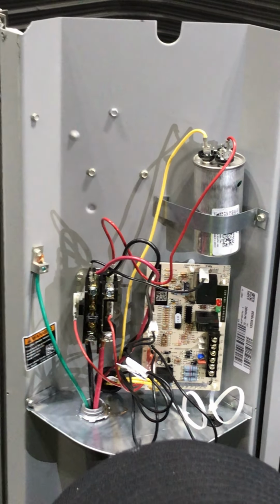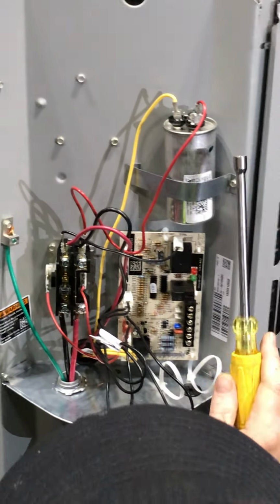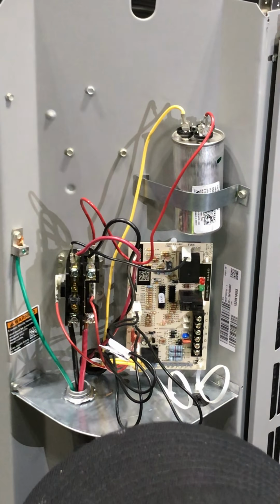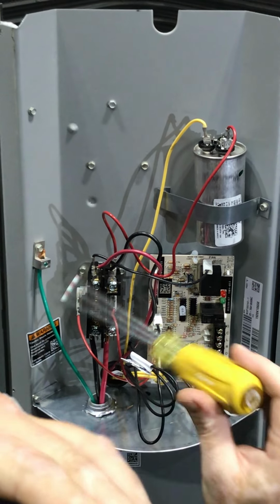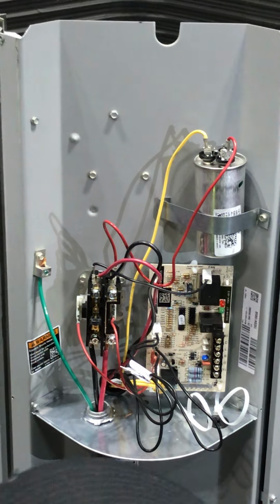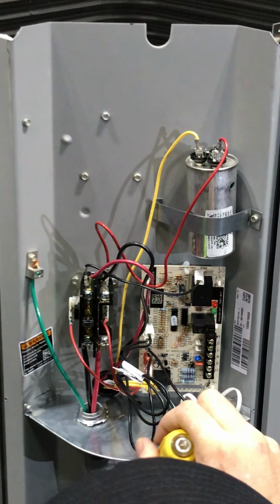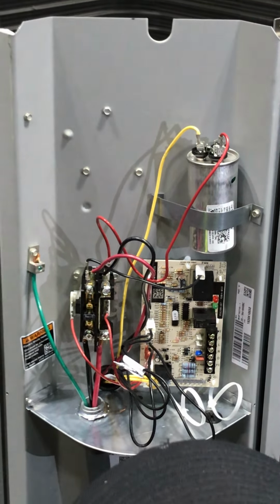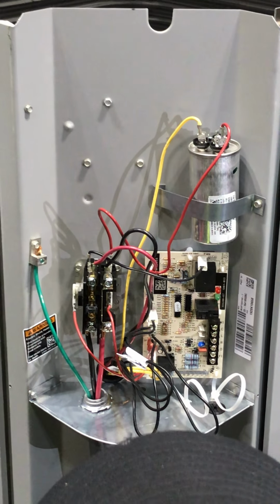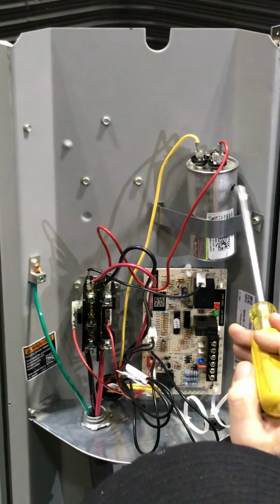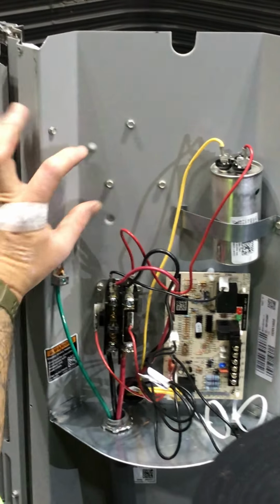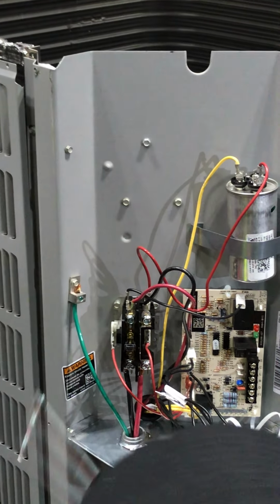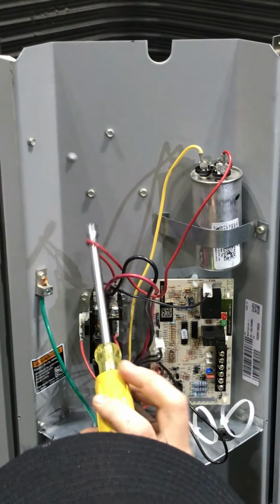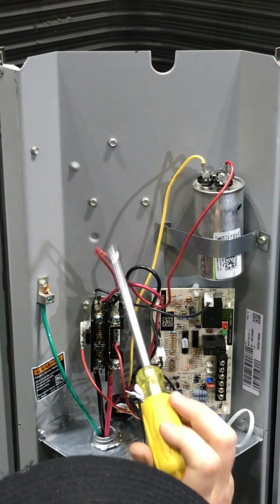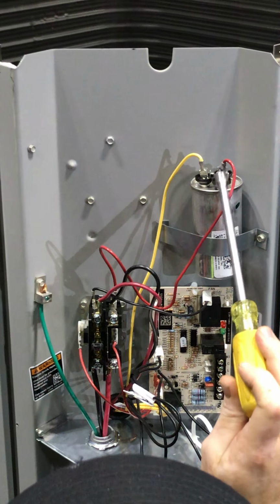So the capacitor only starts the fan, doesn't start the compressor? It starts both. Sometimes you have two capacitors depending on the size of the unit. There'll be one just for the fan and one just for the compressor. Sometimes there's three: a start one just for the compressor and then a run one. It just depends on the unit itself. But most of the time, you're dealing with one. The fan one would be like half the size, and it would just go to the fan. But don't forget this jumper right here, guys. This jumper's easy to forget. This guy sends common.